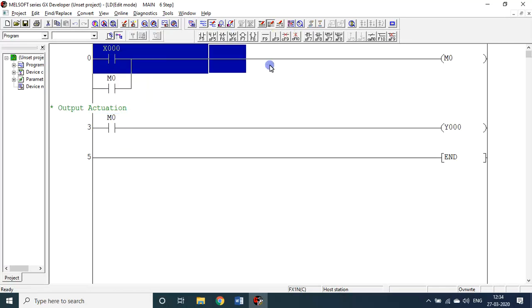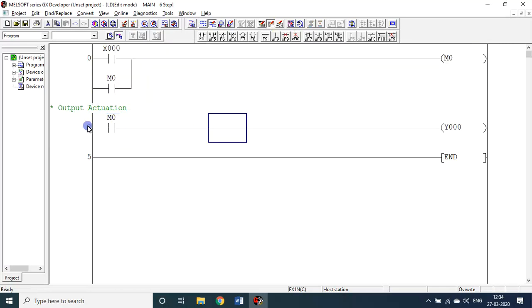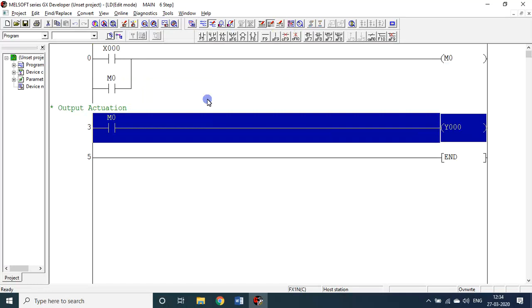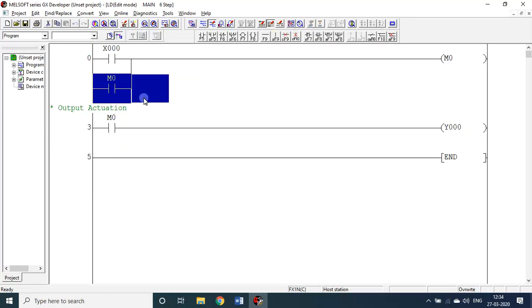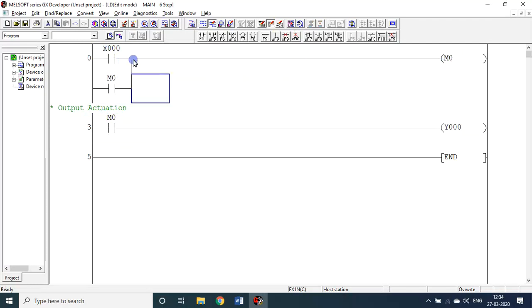There is no result-wise or operational-wise difference between this program and the previous one. In the previous one we had Y in place of M0. Now I introduce M0 — this is a better way of writing a program. Once X0 is on, M0 will be on; if X0 is off, M0 and Y0 will be off. If we put an SR circuit with the same notation, it becomes a latch — once X0 is on, whatever the condition, Y0 or M0 will be permanently on.